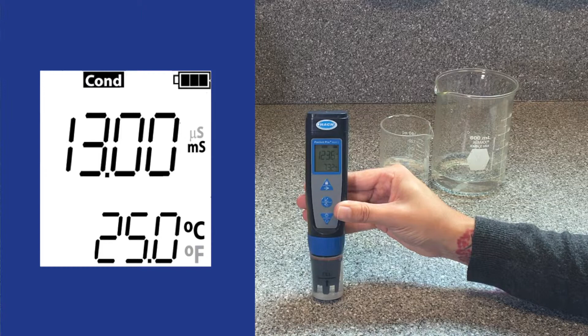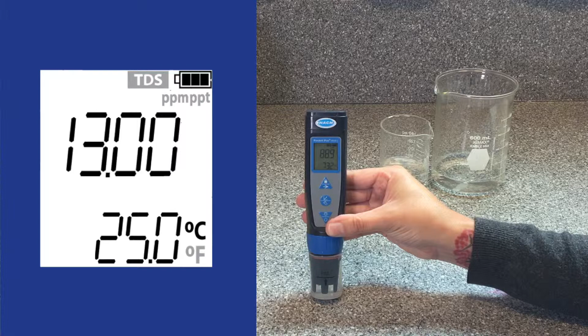The next parameter we will hold again until it switches. The next one is TDS, or total dissolved solids. Again, pay attention to the units. This can be displayed in parts per million, which is ppm, which is also equivalent to milligrams per liter, or it may be shown in parts per thousand, which would show as ppt. Again, we'll push and hold to move to the next parameter, and that's salinity. Again, just like TDS, salinity can be shown as parts per million or parts per thousand, so always write down the value and the units.